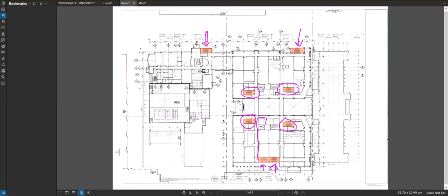So, probably it's the combination of both. Probably it was travel distance that drove having to add these exits in the middle of the building, but as well, it allowed smaller width of exits at the perimeters. And if we looked at the exterior exits, if we entered the stair here and went down to the main floor, doors would open directly to the outside. For these 2 down here, for that one there, and for that one there. That makes sense because they're all on the exterior wall and very easy to achieve that.